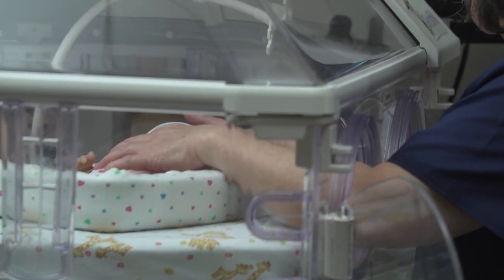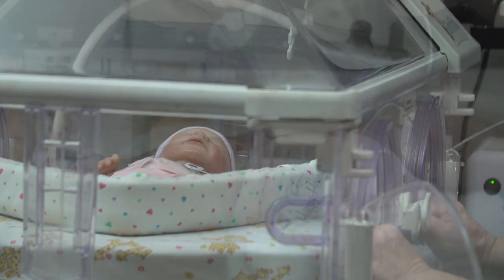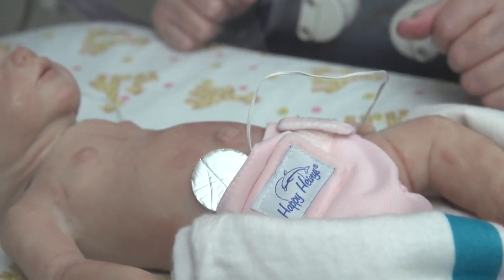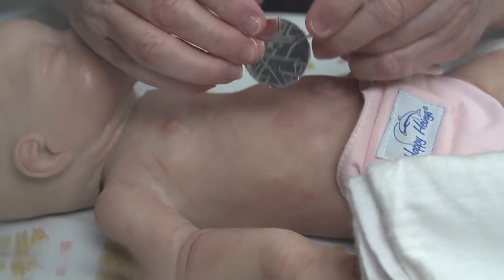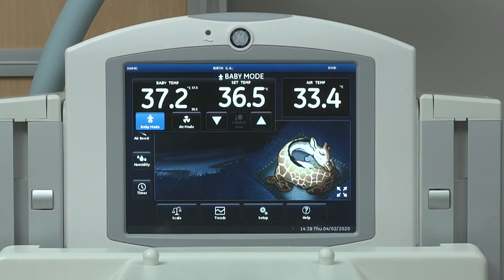If the patient shows more than a typical 0.5 degrees Celsius or 0.9 degrees Fahrenheit difference between the abdominal skin temperature and a remote site such as the axilla or rectum, consider the following actions: verify the skin temperature probe has good skin contact using a reflective patch, move the temperature probe to another site such as the axilla, and continue to monitor the patient's temperature. Adjust the set temperature as needed to meet the desired temperature at the independent measurement site.